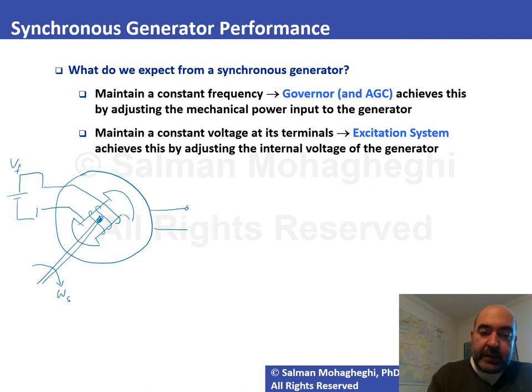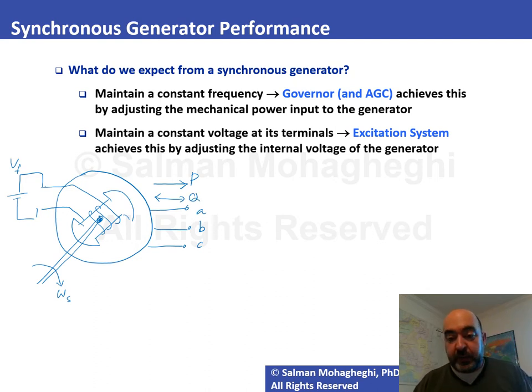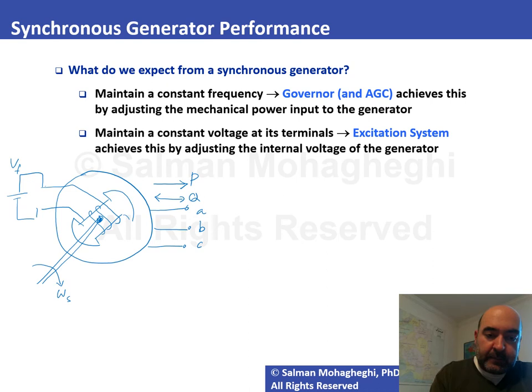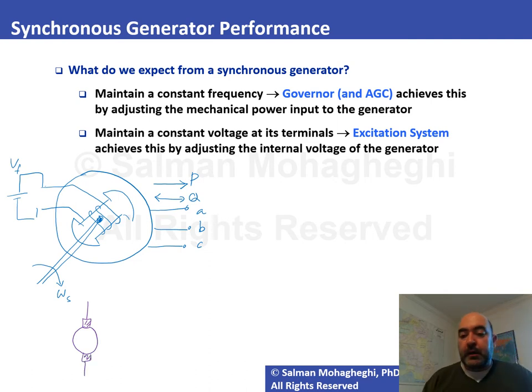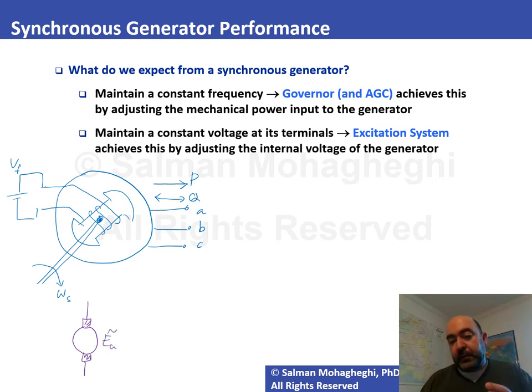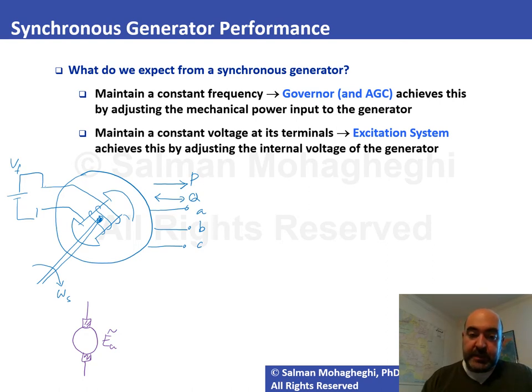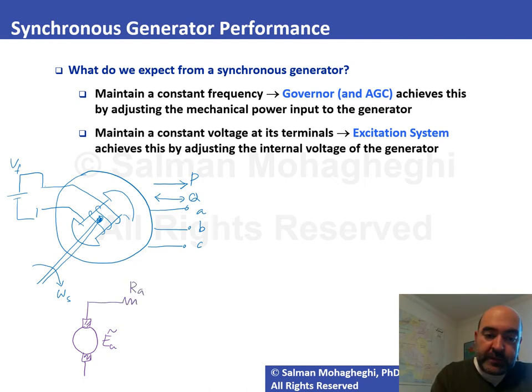The stator has three connections for phases A, B, and C. It injects active power into the grid and either injects or draws reactive power from the grid. We model this as an electrical equivalent circuit, where E_A is the internal voltage induced in the armature — the voltage generated internally in the machine. This is not the terminal voltage because the generator has losses modeled as armature resistance and synchronous reactance.